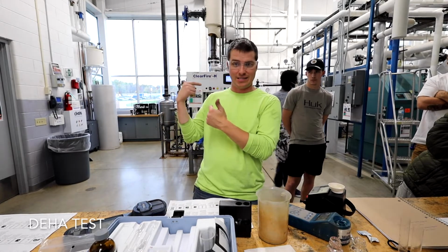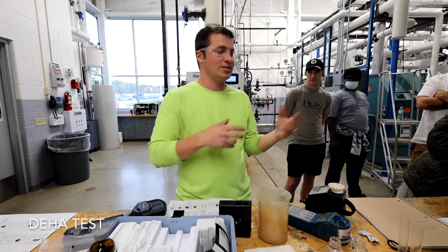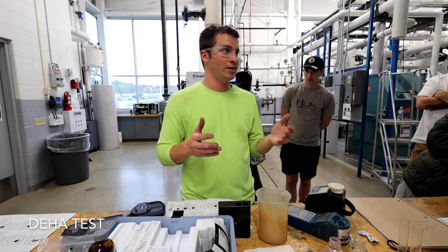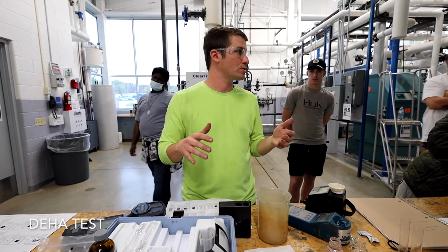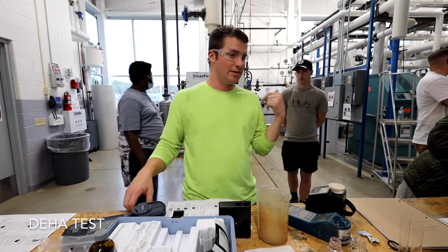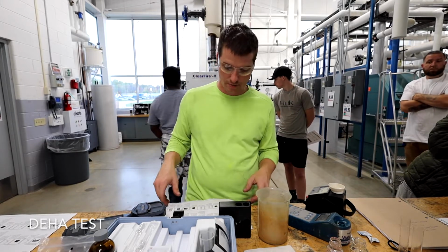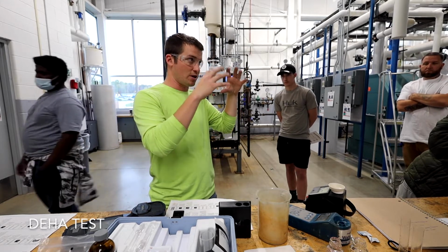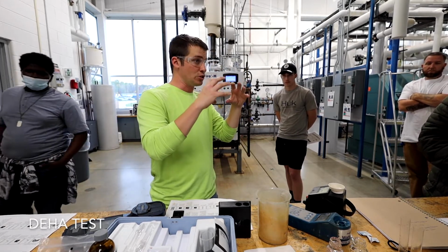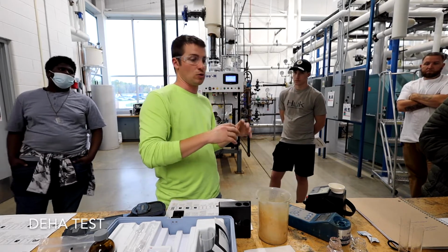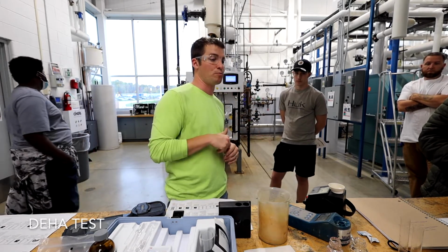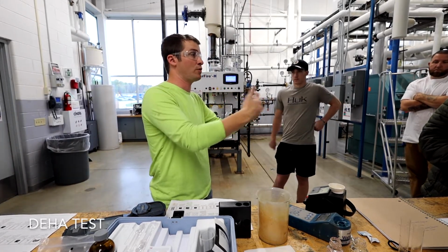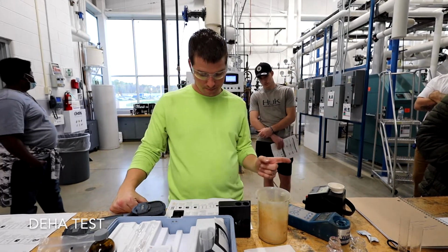So it's cool. It's awesome to get hands-on experience. It's challenging because it doesn't run like a true boiler would run. Boilers are designed to be on and running at like 80% load all the time, right? They're workhorses. They want to just run. This doesn't, so it makes it a little more challenging. Because as the water sits, that feed water tank is going to suck air into it. It's not sealed, so it's going to suck in oxygen. That means it's going to react with the DEHA and just use it up before it even gets into our boiler and does anything. So the only way we can overcome that here is to just feed more product, because you don't have demand to make the system run the way that it should run. Does that make sense? Okay.